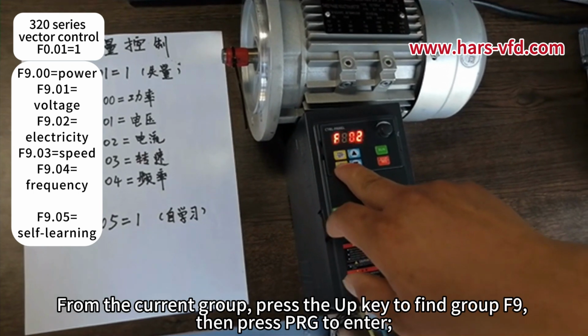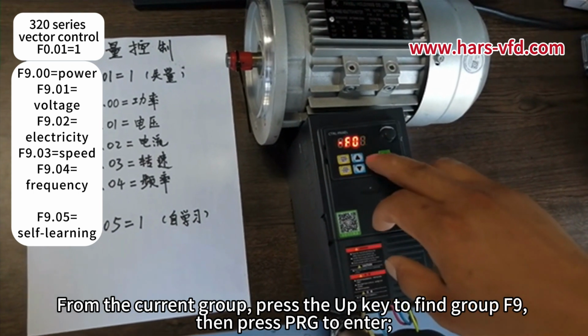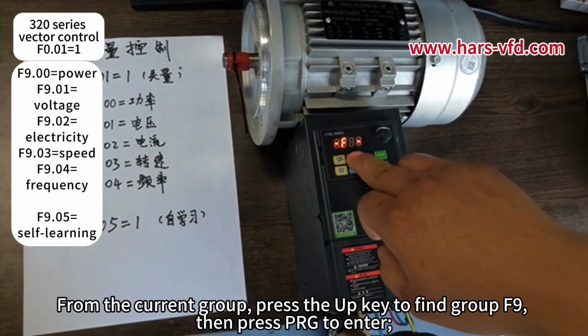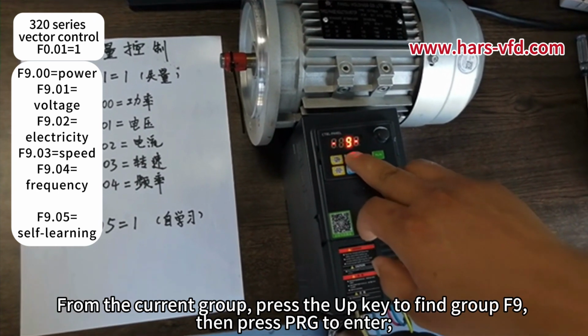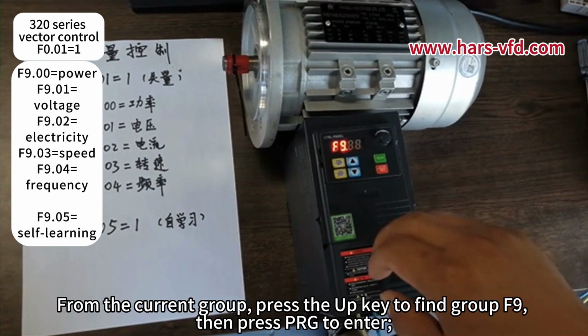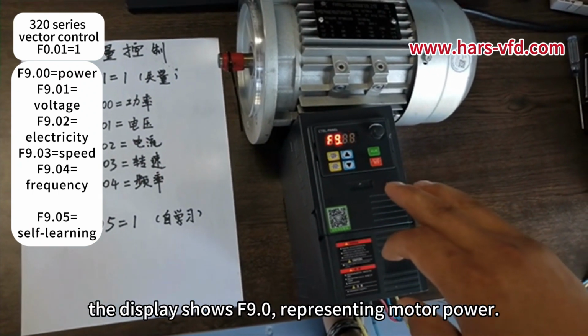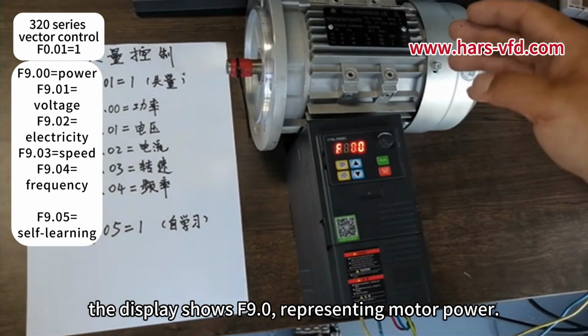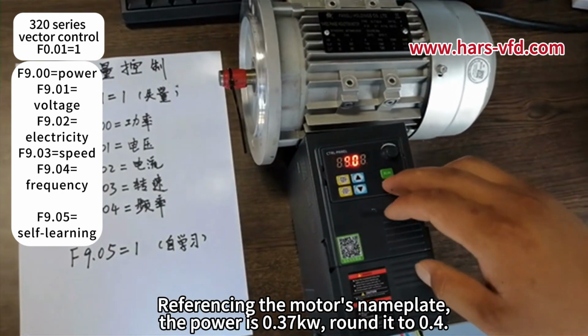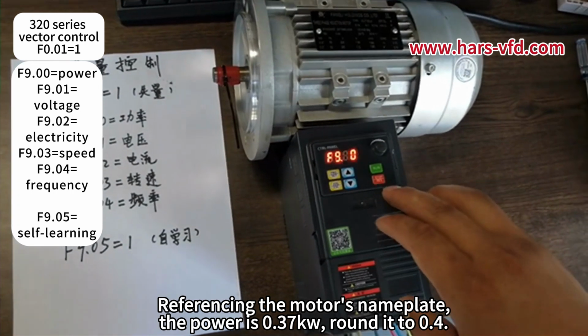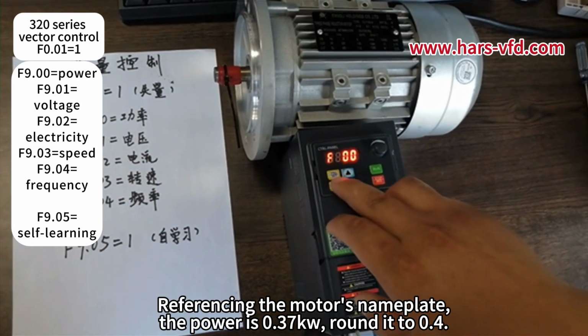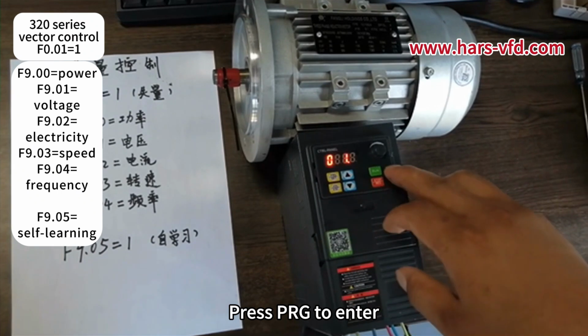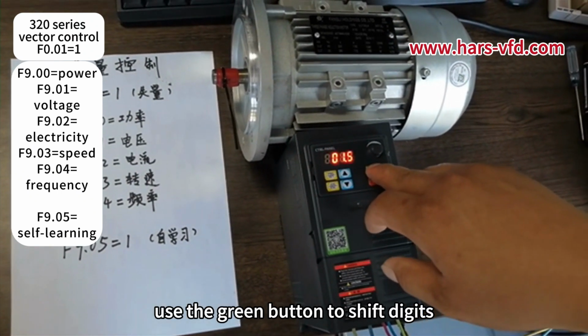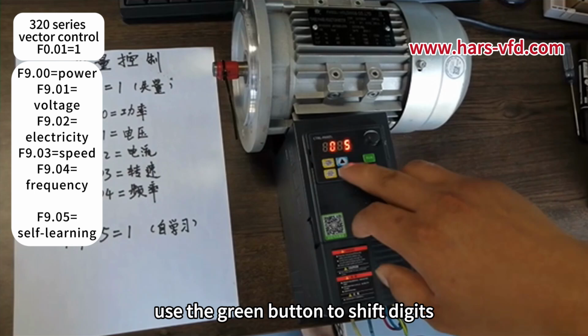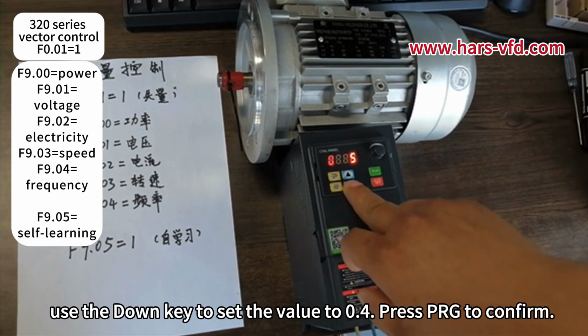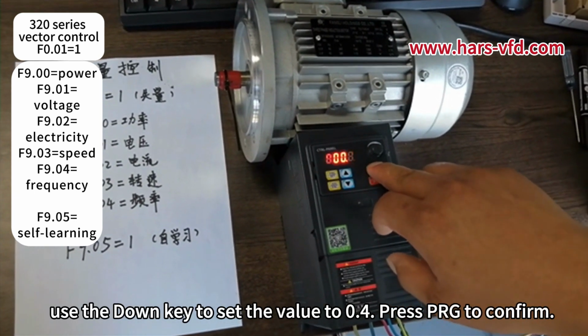From the current group, press the up key to find group F9, then press PRG to enter. The display shows F9.00, representing motor power. Referencing the motor's nameplate, the power is 0.37 kW, round it to 0.4. Press PRG to enter. Use the green button to shift digits. Use the down key to set the value to 0.4. Press PRG to confirm.